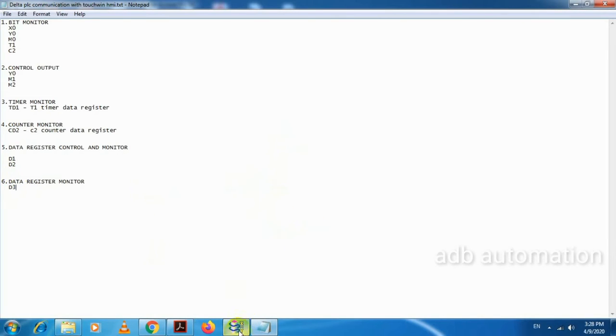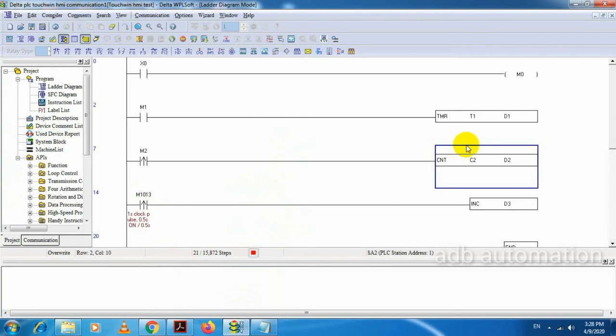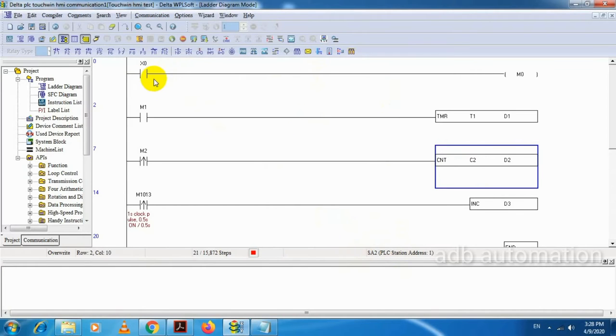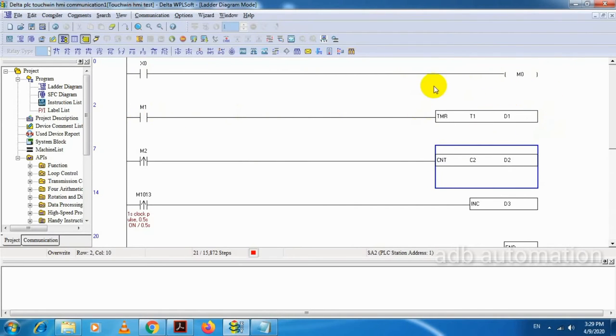Now we will make a program in Delta PLC. I have already made the program. Here I have used Delta PLC SA2 series. Now I will explain this program. If X0 is high, I am making M0 coil on. If M1 is high, then I will run the T1 timer. The timer value I am giving through data register D1, so whatever value I enter in the D1 register, according to that, this timer will run.